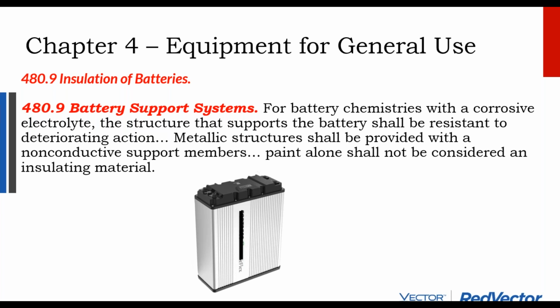I remember on one of my first battery projects, these batteries are very heavy, and we were picking them up with our on-site lift equipment by attaching metal chains to the metal casings of the batteries. And the battery terminals are just sticking out, right there. We had to tape the chains with some rubber resistive tape to chain the batteries to the lift equipment and move them around. Otherwise, we'd get arcing between the battery terminals and the metal chain that could continue to conduct into the metal lift equipment and potentially electrocute the driver.